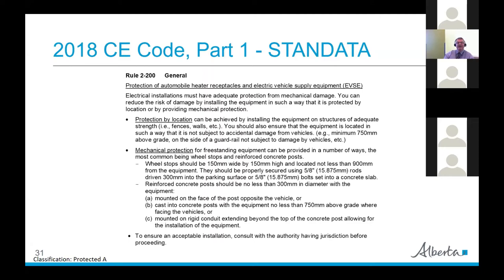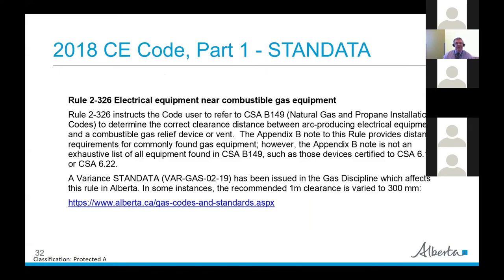We also issued a STANDATA for protection of automobile heater receptacles and added electric vehicle supply equipment. As we all know, electric vehicles are here and ramping up, and we're seeing a lot more EV charging installations. Rule 2-200 previously provided protection for automobile heater receptacles, so we reworded the original STANDATA to include electric vehicle charging equipment that's starting to be installed.